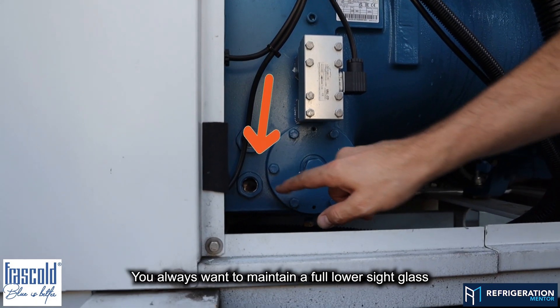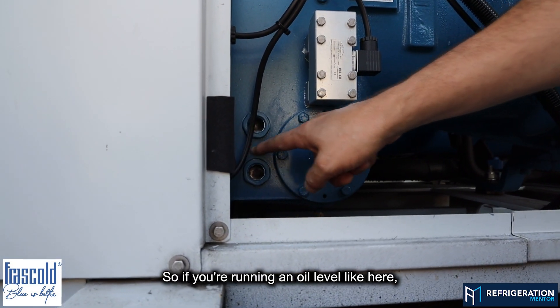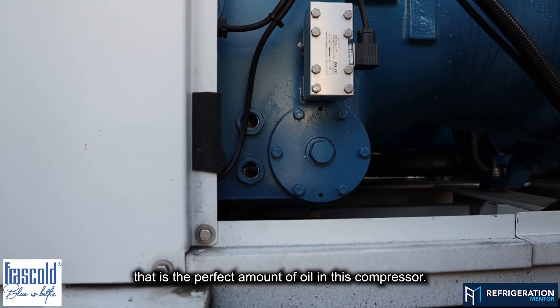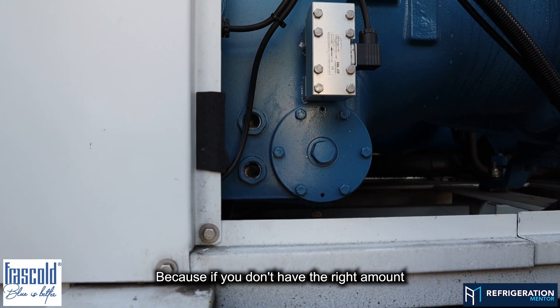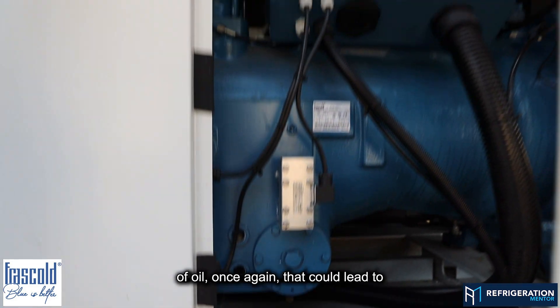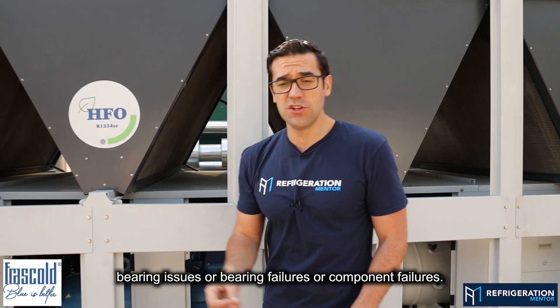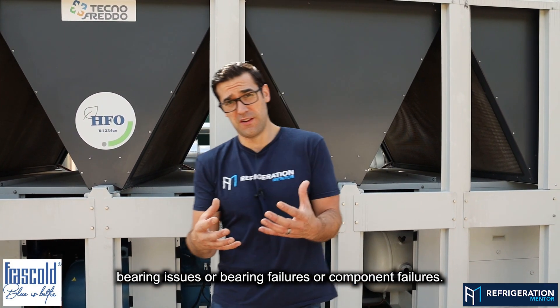You always want to maintain a full lower sight glass. Running an oil level like what's shown here is the perfect amount of oil in this compressor. If you don't have the right amount of oil, that could lead to bearing issues, bearing failures, or component failures.